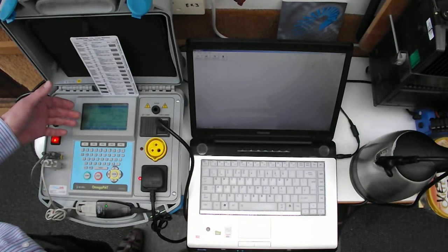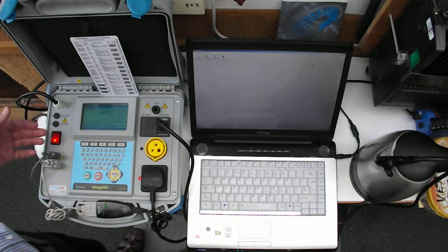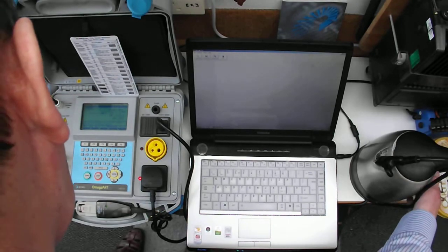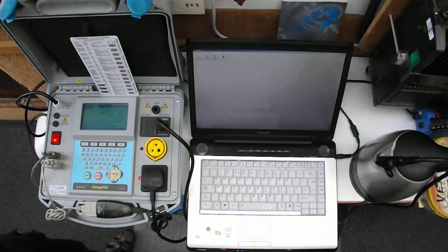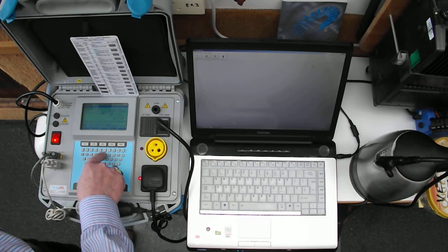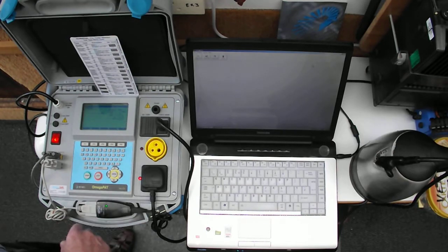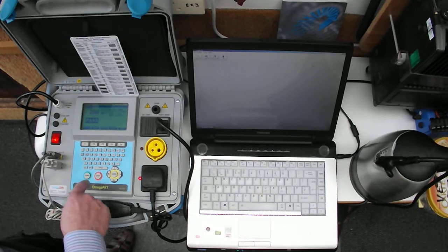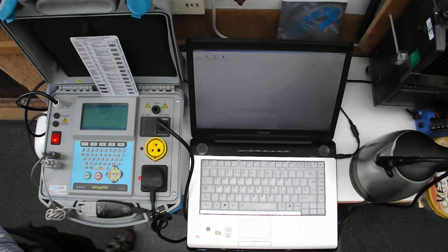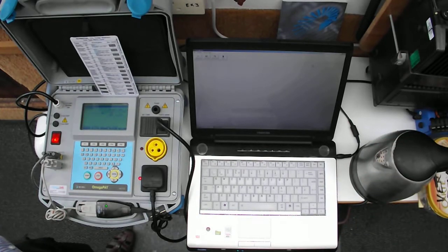Now it's going straight on to the other tests involved, which is the insulation test. Now it's telling us here the resistance is too high, so we haven't turned the kettle on. Turn it on. Are you sure to proceed? Yes. We press Y, and now we're ready. It's going on there to do the impedance test. That's passed, and now we're going to press start. Remember, the kettle's still on. And it's telling us to remove the earth bond clip. We don't need that on there.